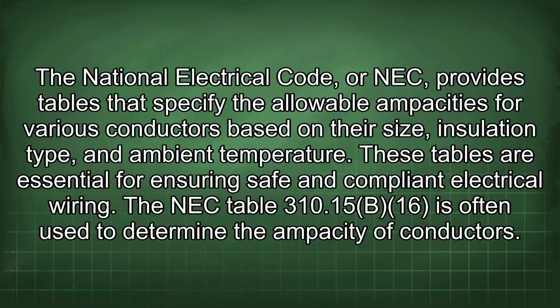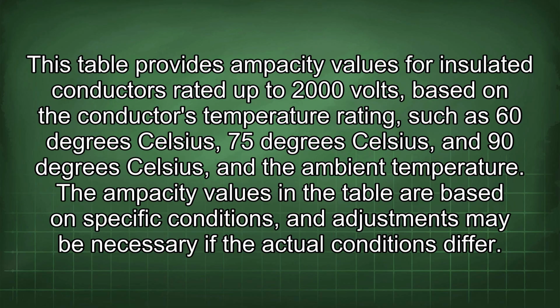The NEC Table 310.15(B)(16) is often used to determine the ampacity of conductors. This table provides ampacity values for insulated conductors rated up to 2000 volts, based on the conductor's temperature rating, such as 60 degrees Celsius, 75 degrees Celsius, and 90 degrees Celsius, and the ambient temperature.